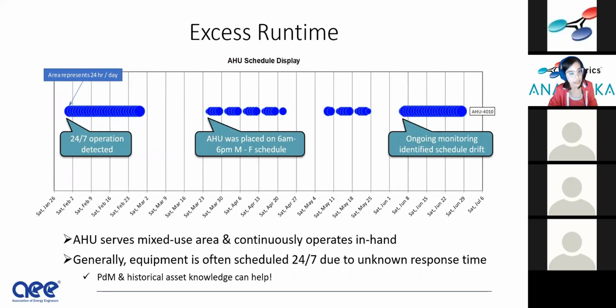Excess runtime, this is a scheduling issue. We use these charts of bubbles. You can see that this size means 24/7 operation. A lot of times we'll see something scheduled, go off schedule, scheduled, go off schedule. We can help understand why is this happening? Why is this unit not staying on schedule? Sometimes it's a change of space use. And we can help identify that.